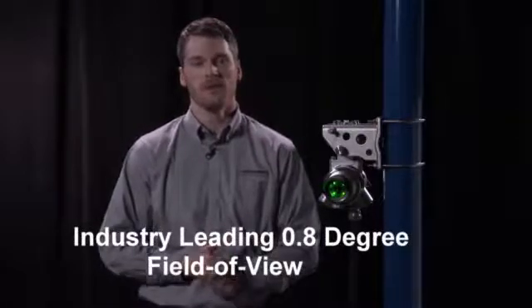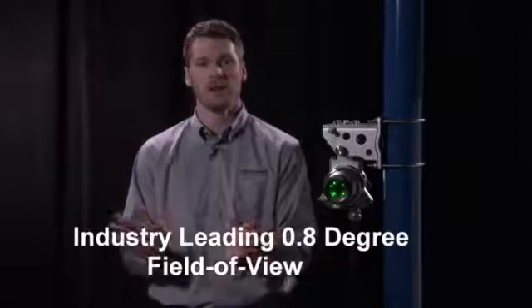The LS2000 has a third-party certified 0.8 degree field of view. That means we can be off axis by 0.8 degrees in any direction and still work properly. The second way we've reduced installation time is we've created a simple and rugged mount. The mount serves two purposes. One is to align the product so that we can get the receiver pointed directly at the transmitter. The second purpose is so that once we get it aligned, we can lock it in tight. I've got two simple adjustments here - adjustment for my vertical direction and adjustment for my horizontal direction. Once I've got the system lined up, I've got a couple locking bolts so I can lock it down tight.